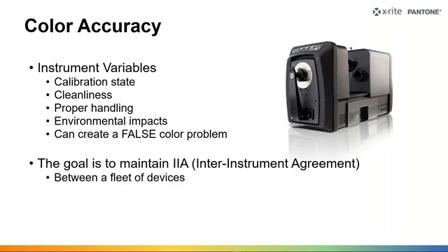They tend to be fairly small, but if that gets out of control by these other variables, then it starts to cause a problem. And it's important to maintain that inter-instrument agreement, especially if you have a fleet of devices. Maybe you have the same device in multiple locations in a single plant, across multiple plants, across the globe, whatever, and you're going to communicate color to each other. You need to be able to have faith that those instruments are maintaining that inter-instrument agreement, so you know that they're reading color the same. It could also be across a supply chain. So maybe it's not just within your own company, but it's a supplier or a customer, right? Who's also measuring the same thing you are. You want to make sure that that's being maintained. And then we talk about those quite often when we talk about inter-instrument agreement, about fleets of devices and supply chains. But maybe this one's the most important.